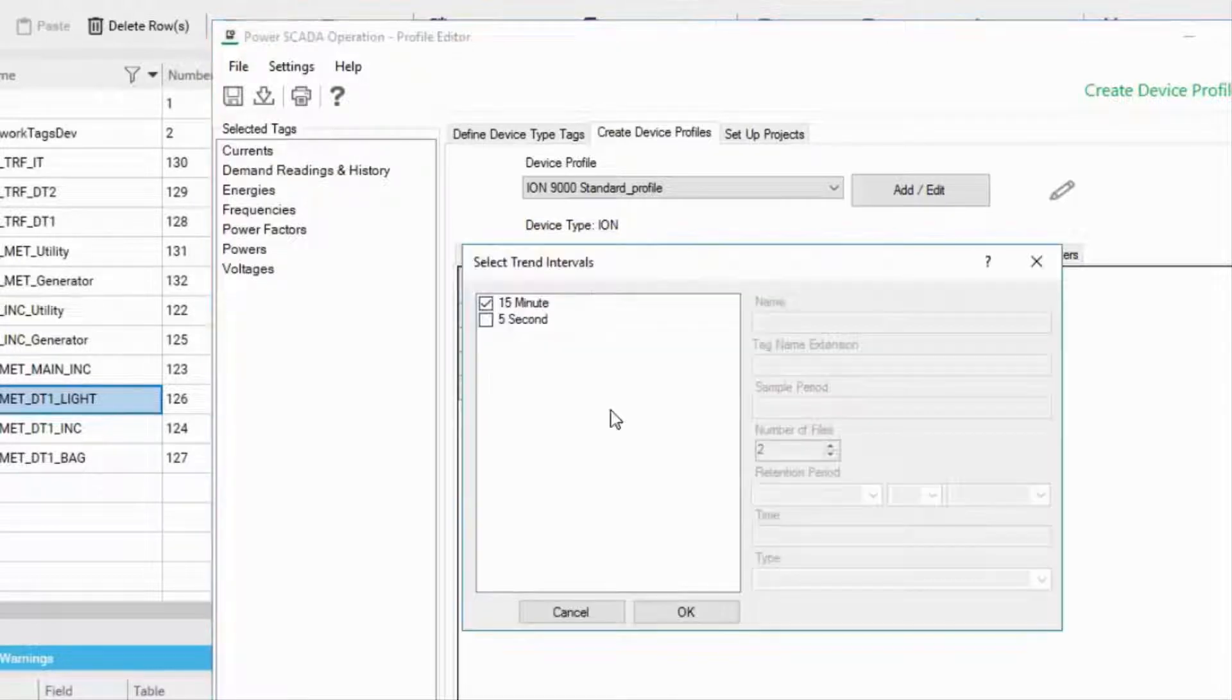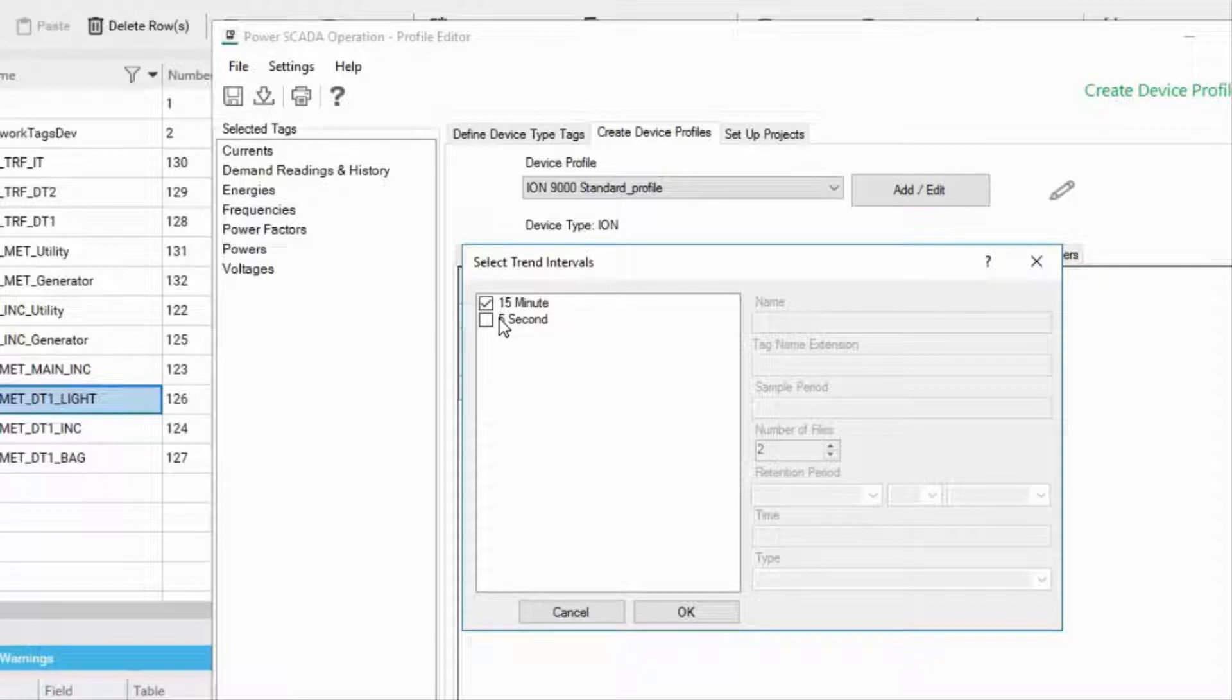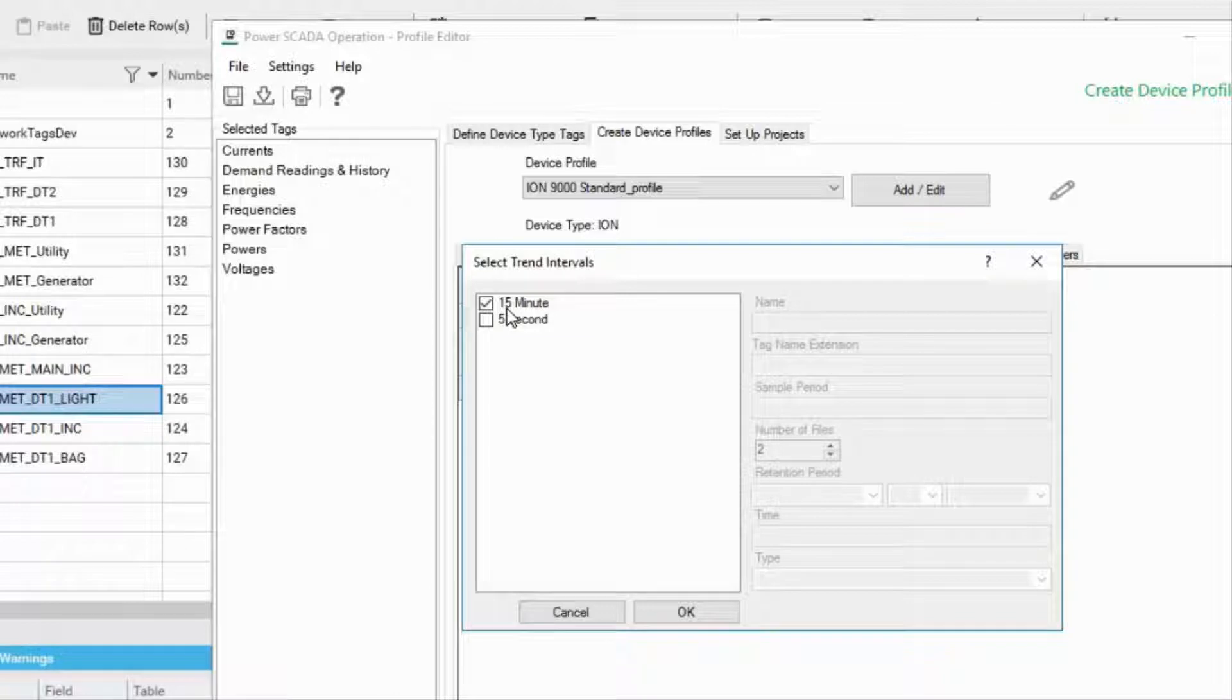When you select a trend tag for a device profile, the tag will be normally scanned at what we call the long interval, that is every 15 minutes with the first in first out storage of 12 months.